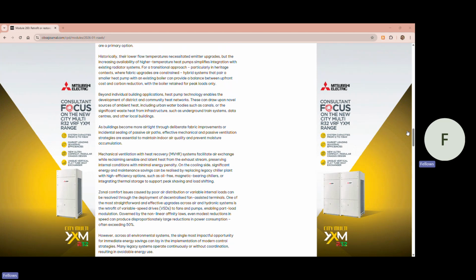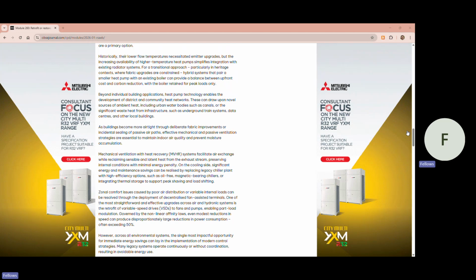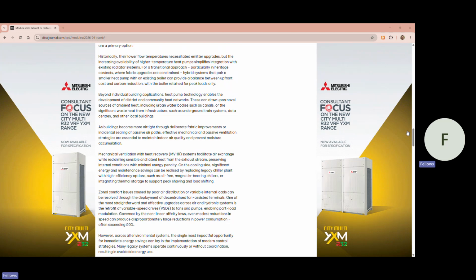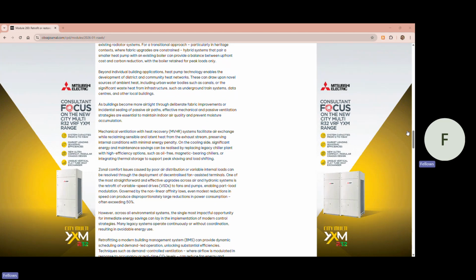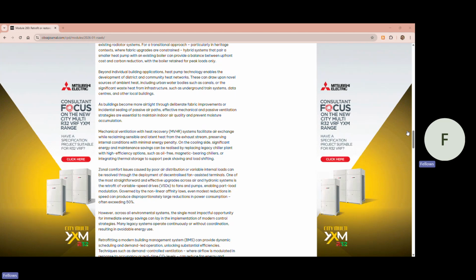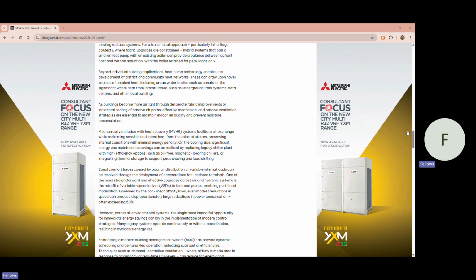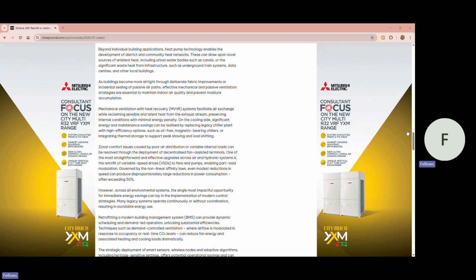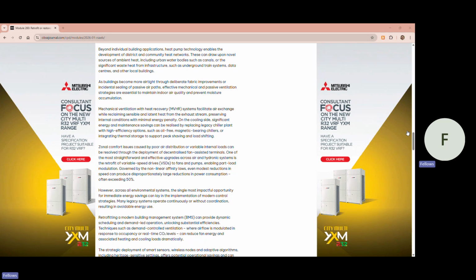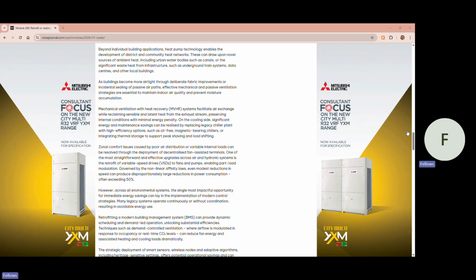As buildings become more airtight through deliberate fabric improvements or incidental sealing of passive air paths, effective mechanical and passive ventilation strategies are essential to maintain indoor air quality and prevent moisture accumulation. Mechanical ventilation with heat recovery (MVHR) systems facilitate air exchange while reclaiming sensible and latent heat from the exhaust stream, preserving internal conditions with minimal energy penalty. On the cooling side, significant energy and maintenance savings can be realized by replacing legacy chiller plants with high efficiency options, such as oil-free magnetic bearing chillers or integrating thermal storage to support peak shaving and load shifting.